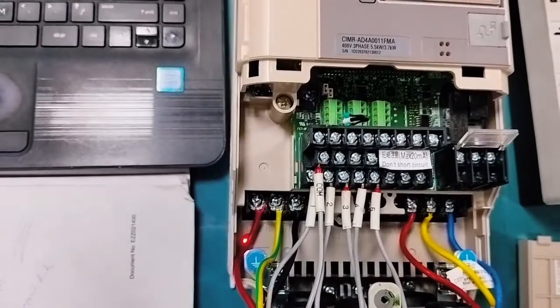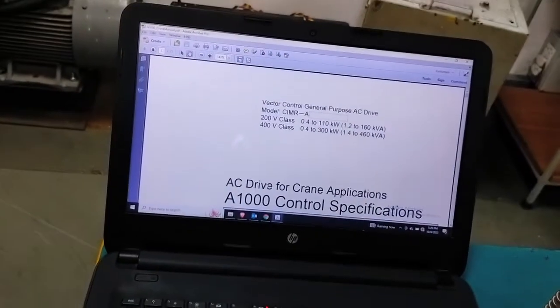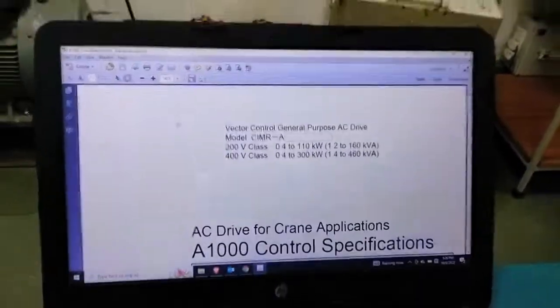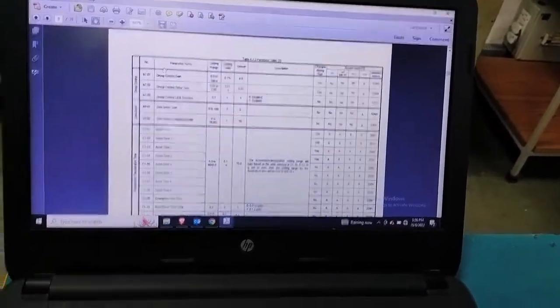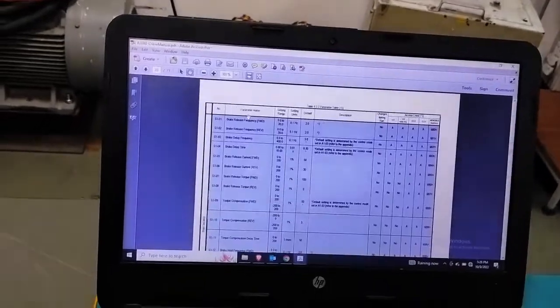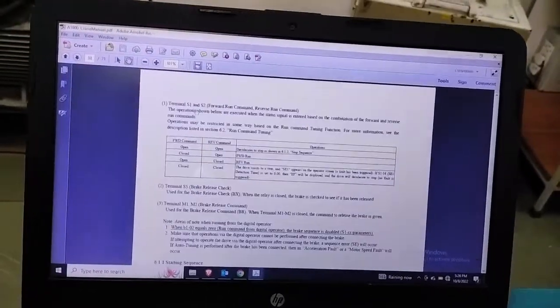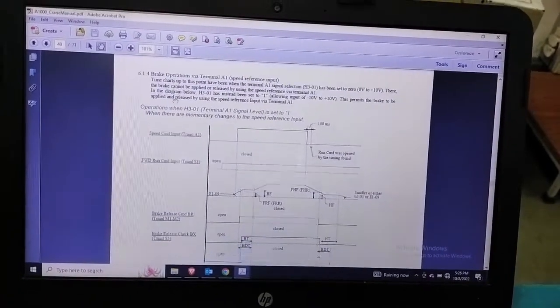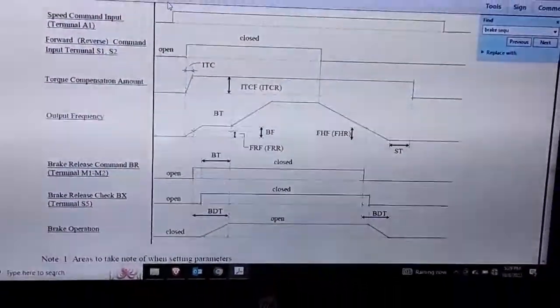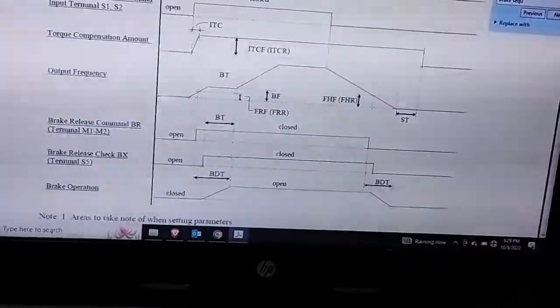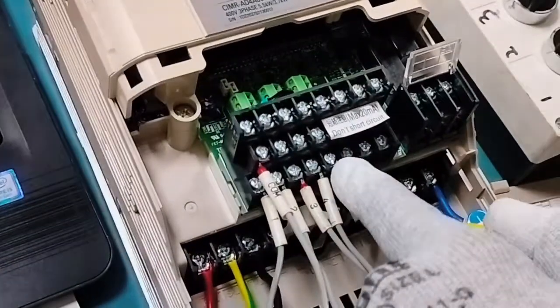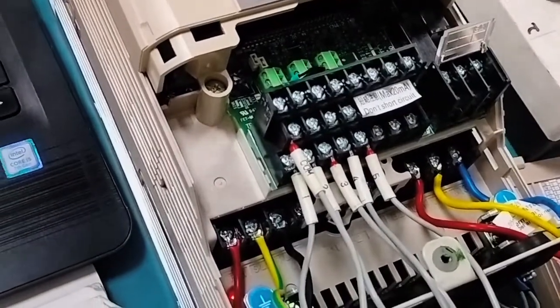I'll show you a simple graph on screen. This is the crane software manual — it comes in hardcopy as well, and it is different from the normal A1000 hardcopy manual. Make sure you have the crane software manual with you when programming. This graph shows the M1/M2 relay, the brake operation, and the feedback from the brake contactor which we have connected on S5.